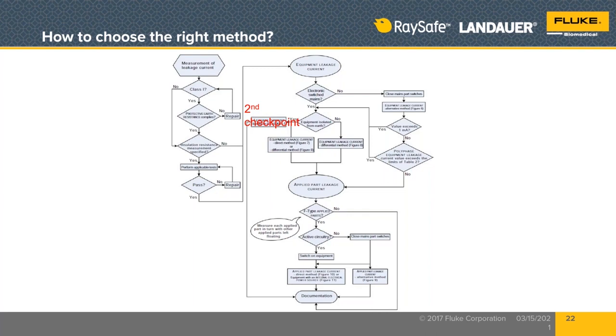So if the device is isolated, you will know that because the patient connections will be an F-type connection, meaning floating or isolated. They will be BF, which is body isolated, or CF, which is isolated for those kinds of patient connections that go directly inside the patient body and typically inside the heart itself. So it's really important. You will know because the medical device manufacturer will disclose that the device is isolated either through markings or symbols on the outside of the device, and certainly in the service manual or test procedures for the medical device that we're testing.